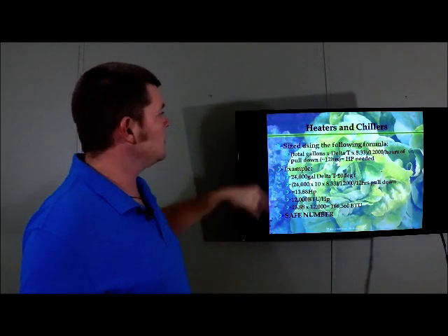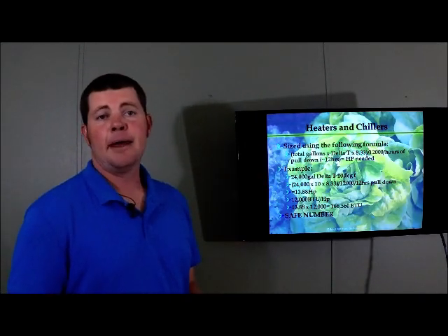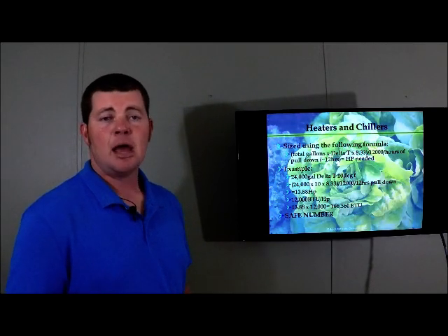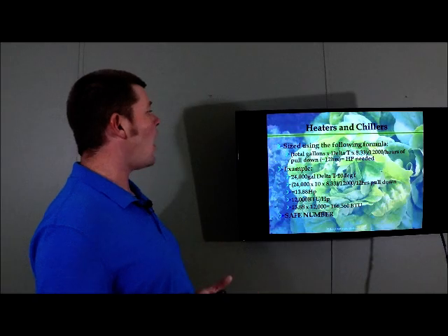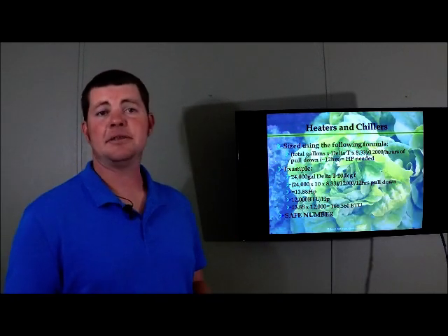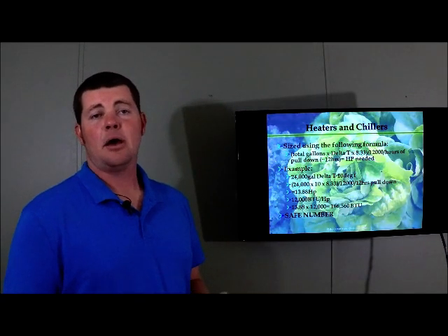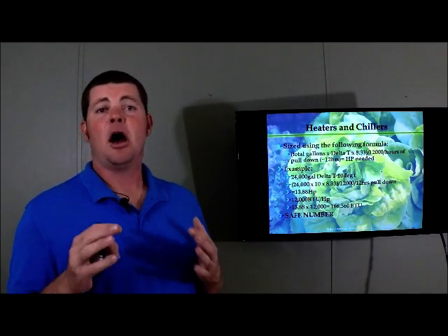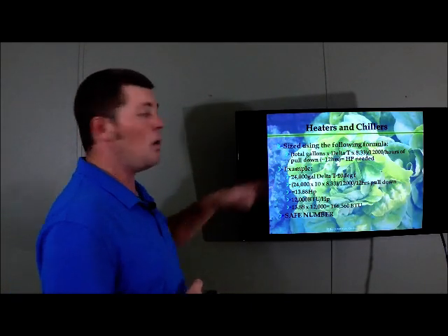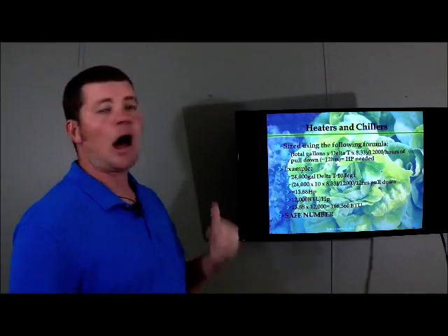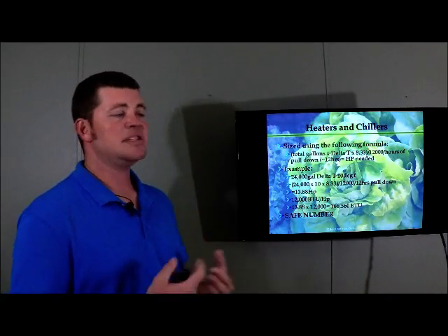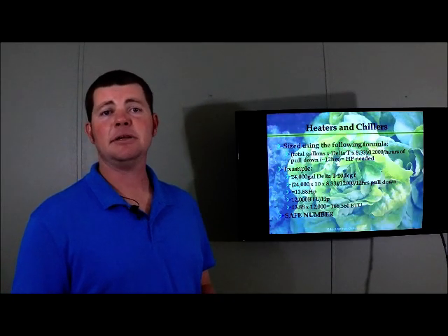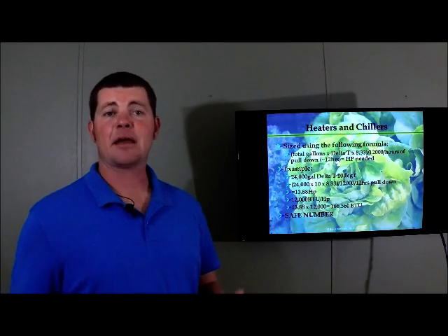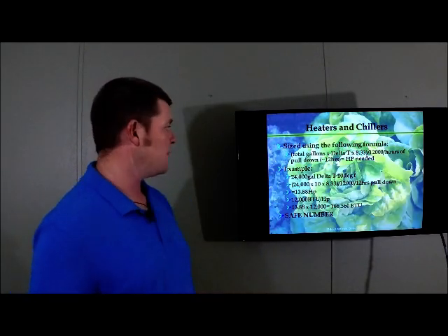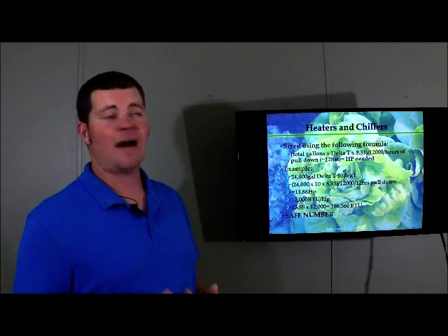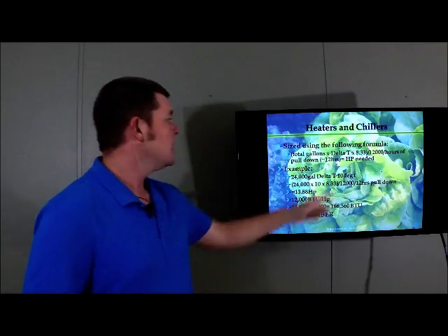And now, if you look up this formula online, you're going to see 24 hours there, okay? That's the main formula you see for temperature change. But within a chilling unit, and because of the water volume we're dealing with, you will not get the desired pull down if you use 24 for that number, okay? Take it from a guy who's seen a lot of undersized chillers in his life. That won't work. So if you take that number and go to Aqualogic or to C-Chill, any of the other chilling manufacturing companies, you're going to see that they will recommend above the number that you calculate using 24. So again, done this a lot, use 12 hours, and that will be a good solid number to give you the horsepower needed.